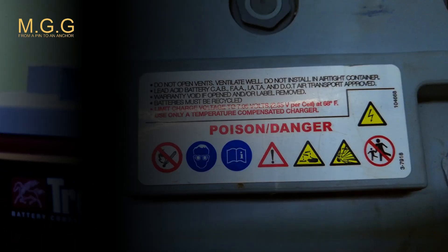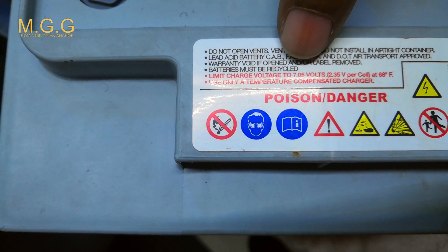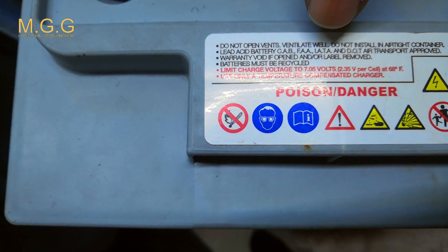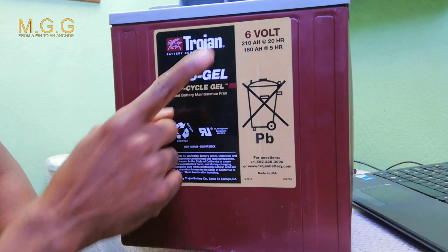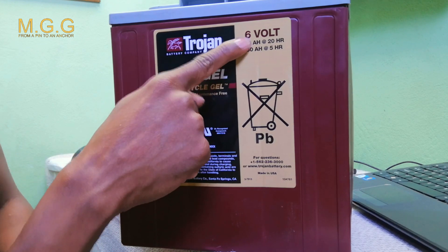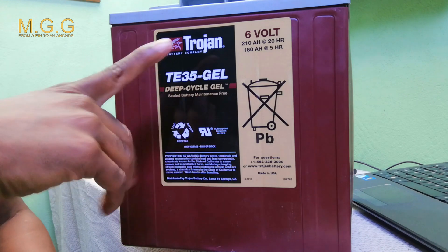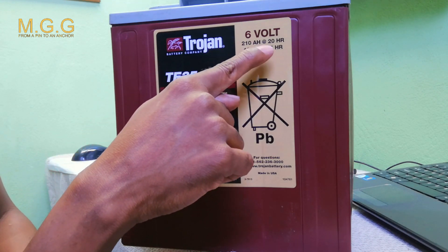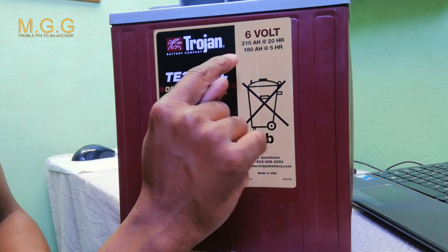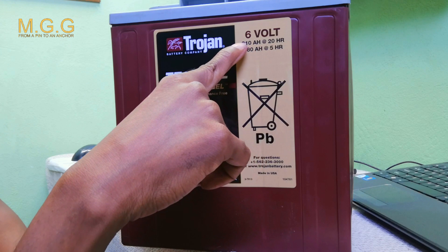Here we have the standard charging method. The limited charging voltage is about 7.05 volts and 2.35 volts per cell. As mentioned, it's a 6 volt battery, which originally charges to 7.05 volts. The capacity is 210 amp hours at 20 hours and 180 amp hours at 5 hours.